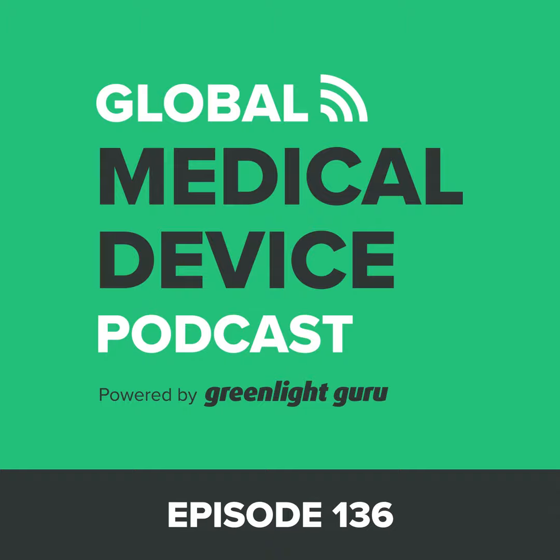And you and I have talked about the RTA in the past. Maybe that would be another topic of an important conversation in the future, because even though the RTA checklist, and by the way, RTA is Refuse to Accept, the checklist has been around for a while, still, as we'll talk about, an awful lot of 510(k) submissions are rejected based on the RTA review, the administrative review. But I think more importantly for our audience to understand, John, is what's the goal of the eSTAR program? Do you think that's something that we should dig into?